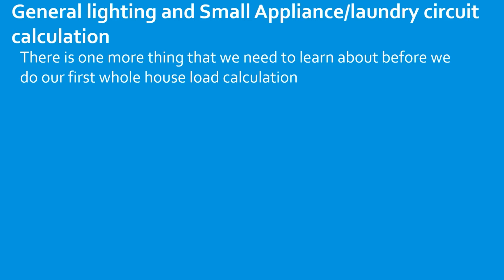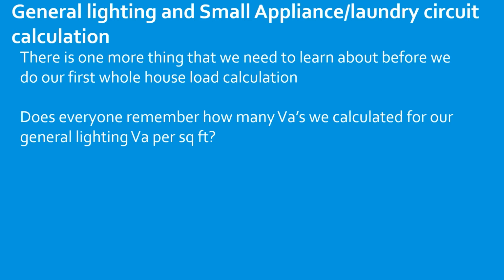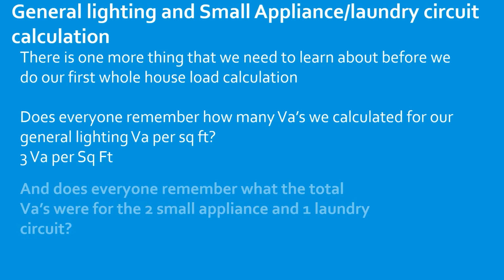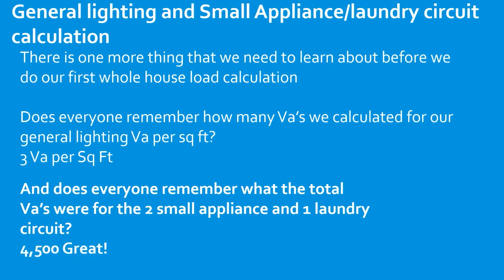All right, y'all, there's just one more thing that we need to learn about before we do our first whole house load calculation, and that's how to apply the demand factors to our general lighting and our small appliance and laundry circuit calculation. Do you guys remember how many VAs it is to calculate per square foot for our square foot VAs? That's right, it's 3. And also, do you remember how many VAs total that we add for our two small appliance and one laundry circuit? That's right, it's 4,500. So we're going to learn how to apply the demand factor to just that section, and then we've got the whole puzzle and we can move on.